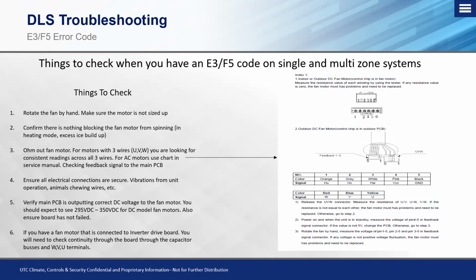The next thing you're going to want to verify is that the main PCB is outputting the correct DC voltage to the fan motor. Okay, on the DC models, you should expect to see about 295 to 350 volts DC for the DC fan motor models. Now, of course, that range is totally dependent on what your incoming AC voltage is. The good rule of thumb is whatever AC voltage you're reading on your main or your bus bar of your outdoor unit, you want to multiply that AC voltage reading by 1.414. Okay, so we think of DC voltage as being 1.414 greater than our incoming AC. That should give you an accurate DC output voltage reading.